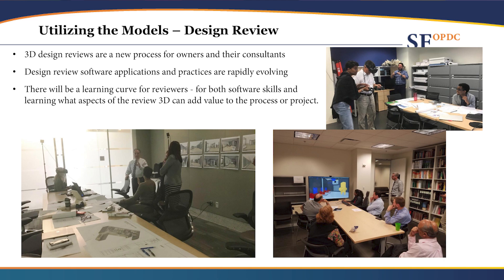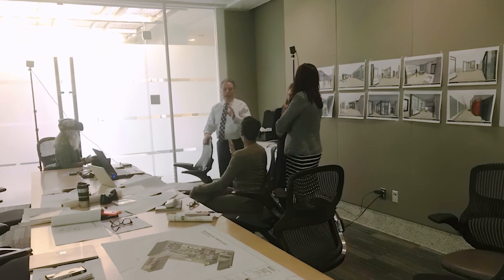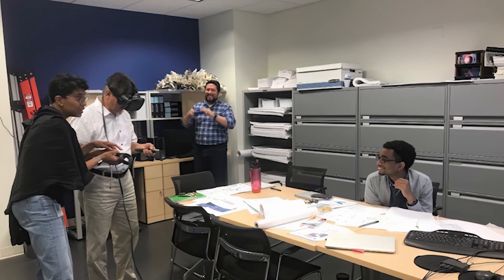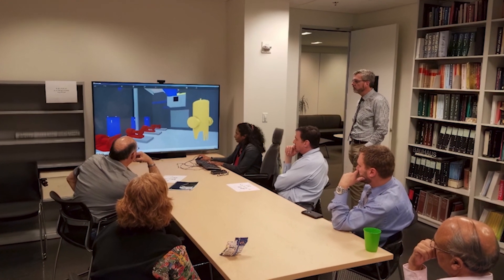I have two stories to share. The first involves technical folks on the National Air and Space Museum project, where we've used Revizto extensively during both design and construction. In a curated immersive design review early in the design phase, my BIM manager was walking them through the mechanical spaces. Within 30 seconds of being placed in the space where the boilers are, they all commented that the boilers needed to rotate 180 degrees — they couldn't access the correct side. That finding helped us avoid a change order, which had happened to us on a previous project.